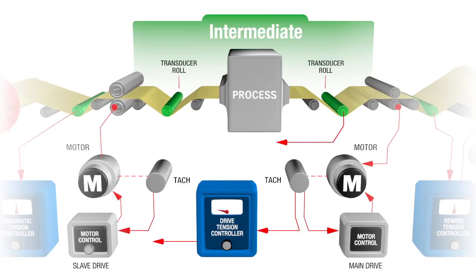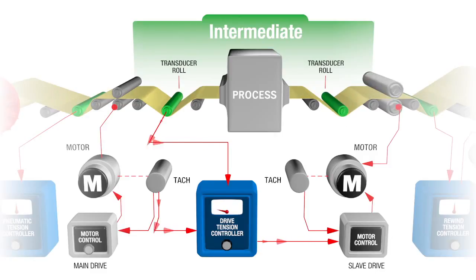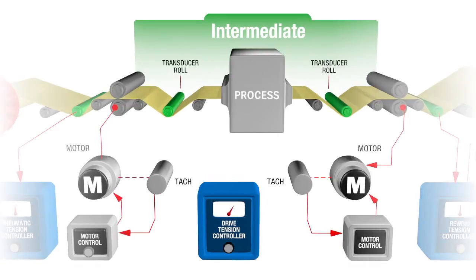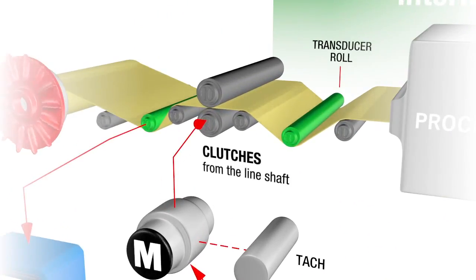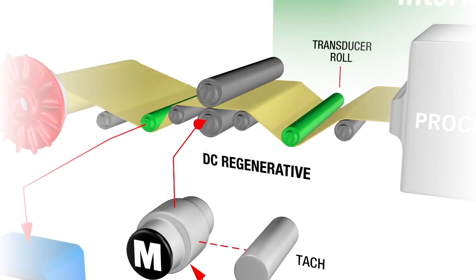When controlling a nip prior to the main drive, the tension controller output slows down the nip to create the correct tension with respect to the main drive section. If the tension-controlled nip is situated after the main drive, then the output increases the nip speed to create tension. Each section must have a positive grip on the web. Nips can be driven by clutches from the line shaft, or by a DC regenerative, AC vector, or servo drive.